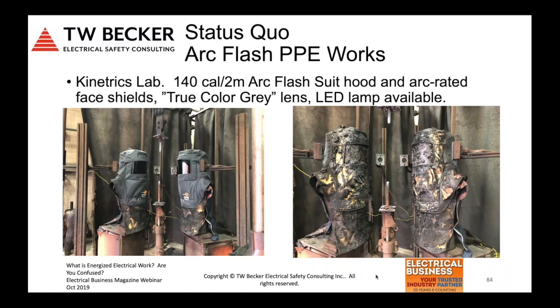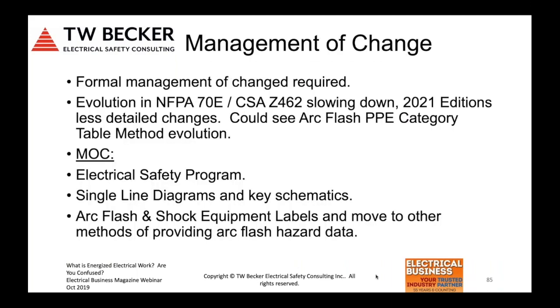Arc flash suit hoods on the left on a test apparatus at the Kinetrics lab. These are 140 cal arc flash suits, and on the right, when they've received, and this is a significant instant energy, we're talking 140 cals of exposure, so it does significant outer layer damage. But again, the worker underneath, when arc flashed at 140 cals, would have the 50% probability of the onset of a second-degree burn injury. Manage the change related to everything that you've done.